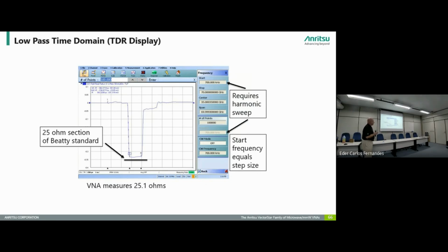This is what we call a Beatty standard. This is a handy device to use to demonstrate the capabilities of the step response low pass time domain. We can profile the impedance. Under normal conditions, this would be the 50 ohms here. Then there's a section where it transforms to 25, and we can pick that out in the TDR display, and then it goes back to 50 ohms. This kind of information is available in time domain that you wouldn't see out of the frequency domain side. But I have to say, time domain is still one of those things that's not as well understood by most VNA users. But the power of it is actually quite impressive, what you can get in terms of troubleshooting capability.